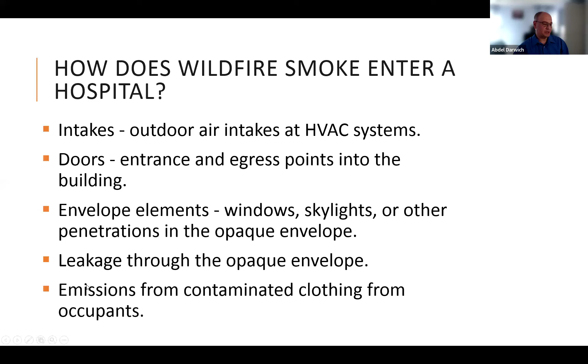Every HVAC unit usually has an outside air intake, and it is usually a source of wildfire smoke entry into the building. So the mitigation is you need to minimize outside air, but don't completely shut outside air. I've seen some people shut outside air. The problem is that if you completely shut outside air, which is used to dilute the indoor contaminants, your indoor contaminants from people, from the walls, from everything, will shoot up. And you may get to a situation where some contaminants may reach unhealthy conditions. So don't do that.